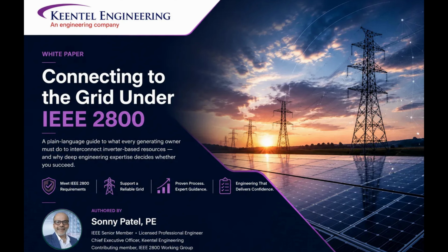Inverter-based resources, solar, wind, and battery storage now make up a huge and growing share of what's connecting to the grid. Unlike traditional spinning generators, they carry almost no physical inertia. When something goes wrong on the system, they react in milliseconds, not seconds. IEEE 2800-2022 sets uniform performance requirements for how these resources have to behave. And here's the part that catches people off guard. If you own the project, compliance is your responsibility, not your equipment vendors, not your EPC contractors. You can hand off the work, but you can't hand off the accountability.